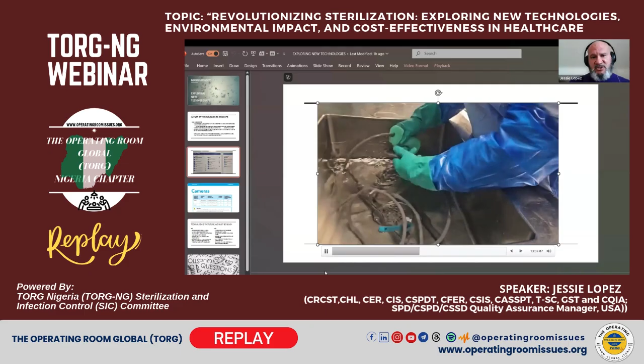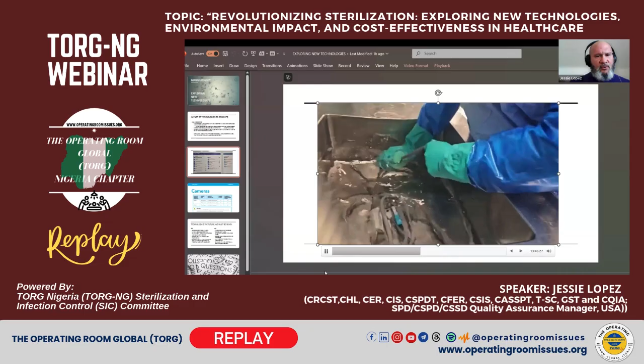Being that this cord is so long, it can be cumbersome. This is why we do one device at a time, to avoid any entanglement of the cords and any possible damage and unnecessary banging of the device. So using our sponge, we're going to transfer over to our soft bristle brush, get the electrical components in that end there, and get around any junctions and connections, because again, we're not going to get that very good with a sponge here.